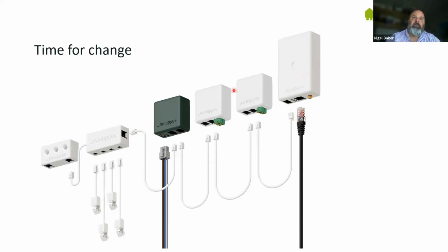The other option we have, you can actually add the Smappee MID meter, and that counts as 3 current transformers because it's a 3-phase meter, and you can then use that as a DIN rail 100 amp direct meter as well. So there are quite a lot of ways of putting a Smappee together. 100 meters from the last CT to the power box, and the gateways can be 100 meters away from the power box as well.